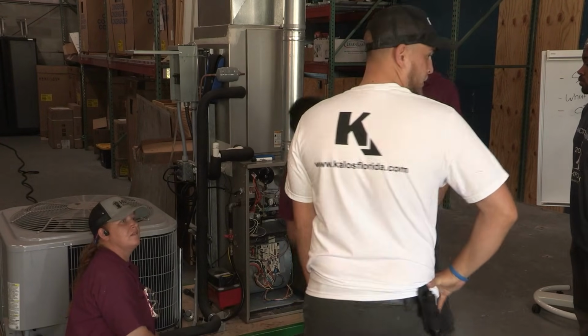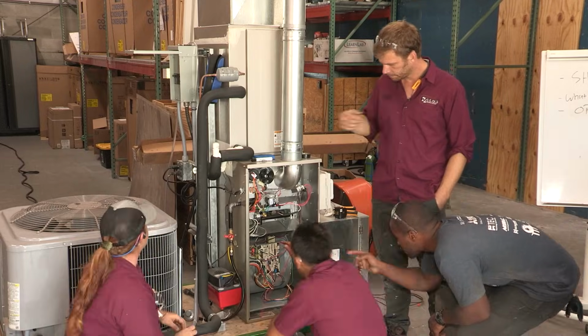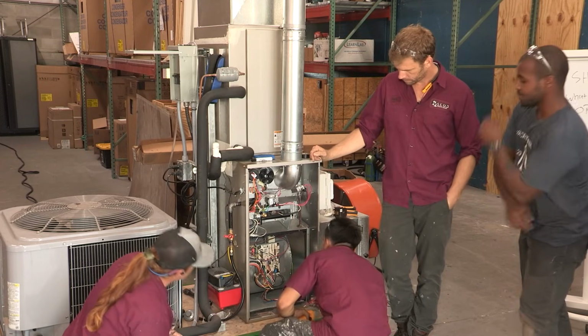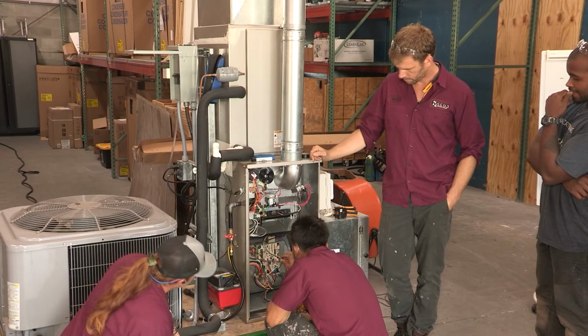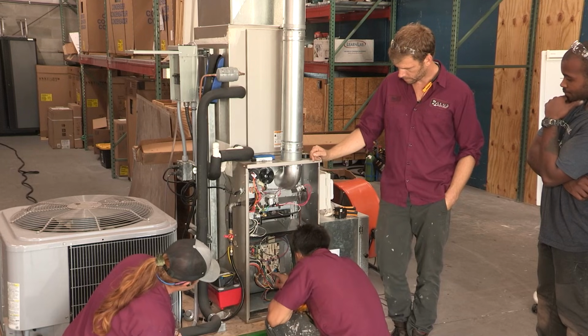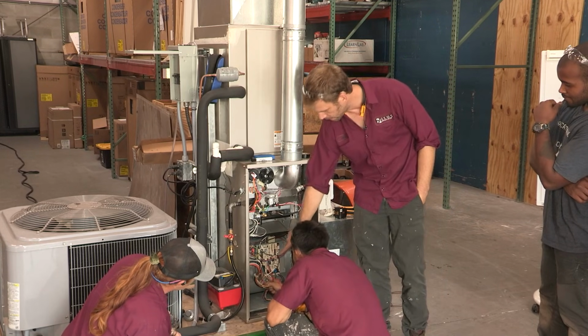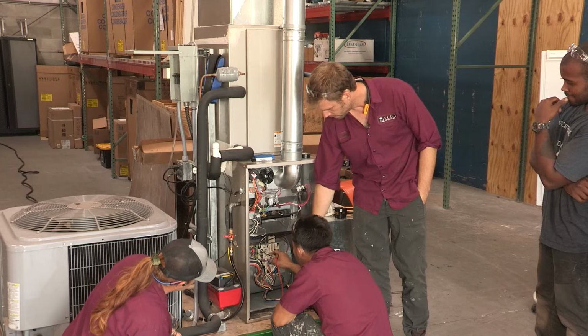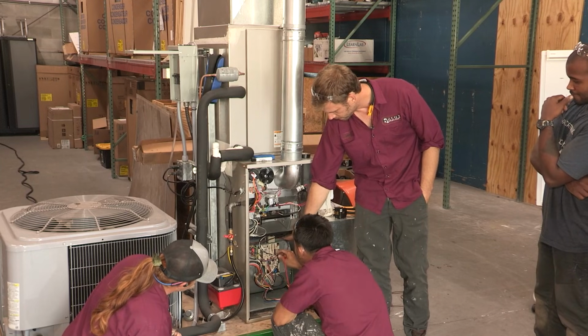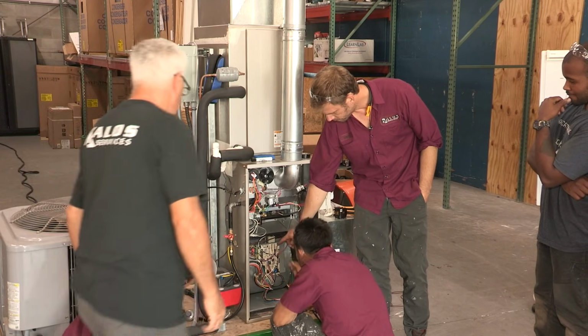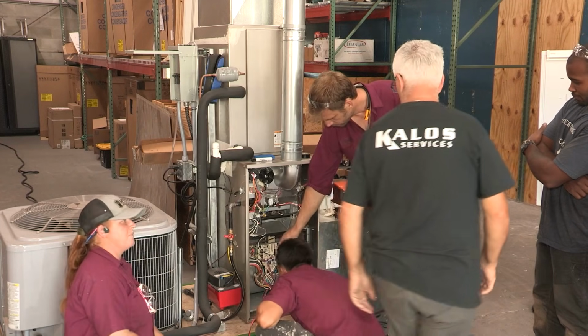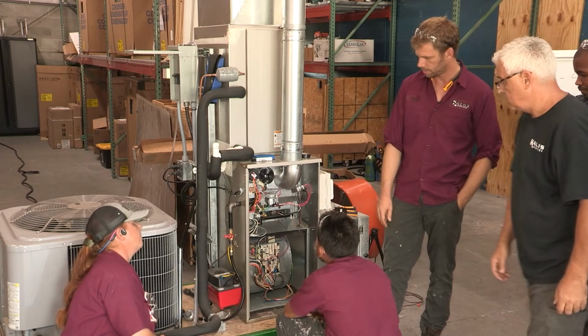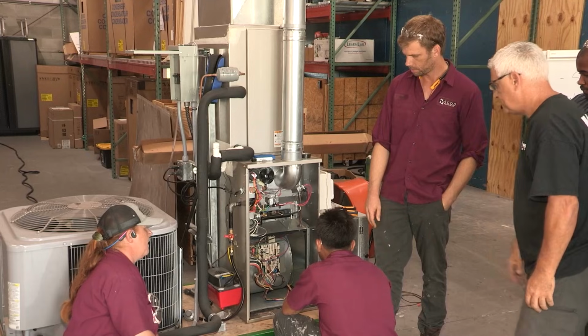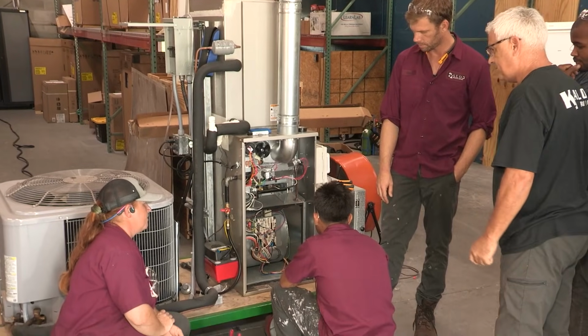Where's the transformer plugging into the board here? Right behind it. So it's coming through here. This is our power supply to it, this is the high side, and then the 24 volts comes out the other side to the reversing valve, right here on red and blue. So that's where you could check if you have voltage coming out of the transformer.